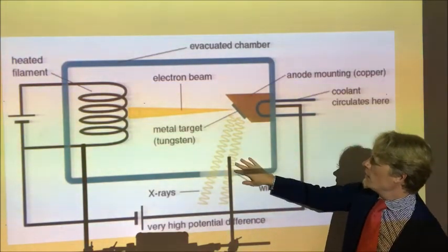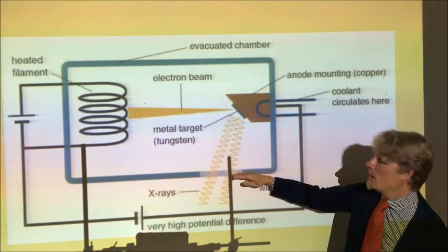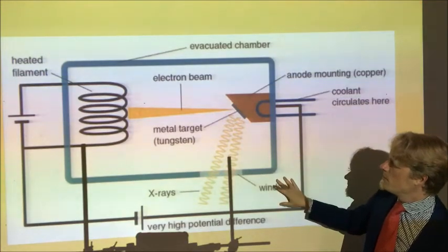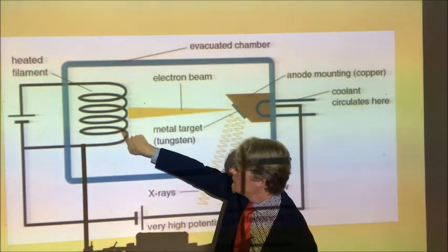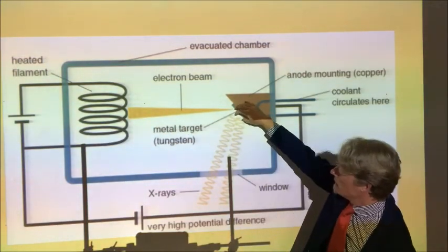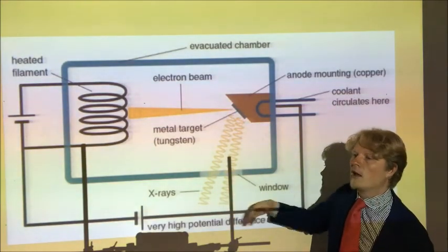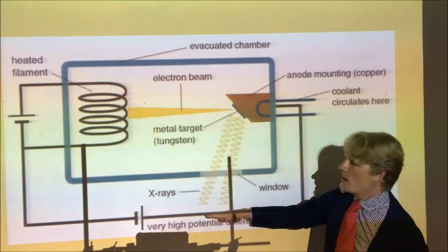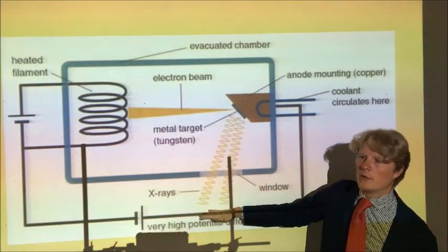So a more intense ray, not image, a more intense ray, is produced probably by producing more electrons, and that will be about turning the current up. So literally more electrons are boiled off and then accelerated over here. The more electrons there are here, the more photons there are per second. That means a higher intensity of ray, and I can perhaps make that image a little faster, and maybe I'm looking after my patient a little bit more when I do that.